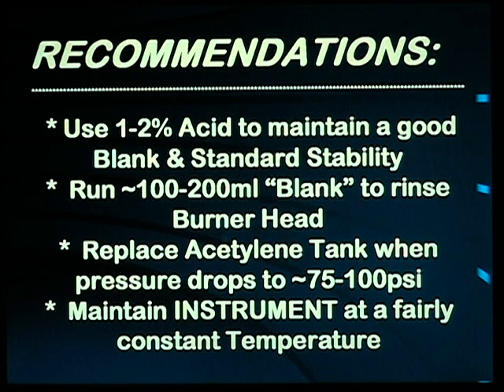Buck Scientific recommends using a good reference book for atomic absorption spectroscopy to give you guidelines for sample preparation and calibration information. For best stability and good blank recoveries, it is recommended that 1 to 2% of either nitric or hydrochloric acid be used in all solutions to prevent hydrolysis and precipitation. At the end of running any high solid samples or high salt materials, run approximately 100 milliliters of your blank or deionized water to rinse out the burner head and the spray chamber to avoid carryover contamination.